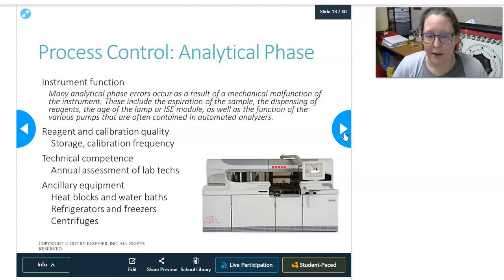Technical competence of your staff. There's usually an annual assessment of lab techs that are operating that machine to make sure that they know how to properly do things such as maintenance and replacing or refeeding basic things like cuvettes, or emptying waste out of that machine, or reloading different fluids and reagents and all of these things. So yeah, every year techs have to go through a competency checklist of some sort for every piece of equipment that they run. And then the ancillary equipment, or equipment that is related to the functioning of the analyzers. And so this could be like heat blocks or water baths if you have to warm something up.